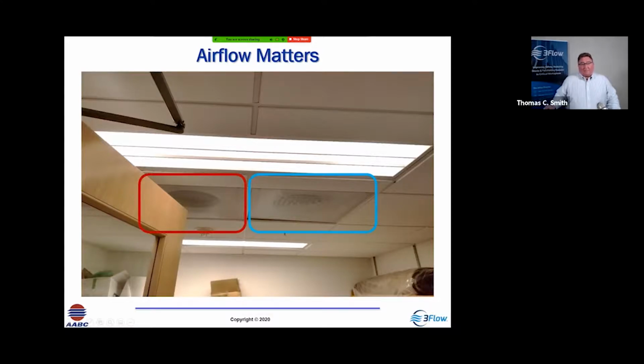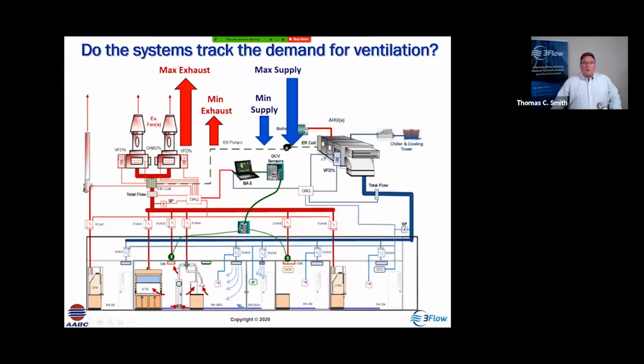So now, we've looked at the hood and the lab. Let's move up to the system. We anticipate that when we're opening and closing, that flow modulates through the hood. But in order to save energy, we have to reduce flow through the fans and through the air handlers. And so how well does the system track the changes in performance at the hood? Is it 1-to-1? Is it 100% sensitivity? Or is there some variation?